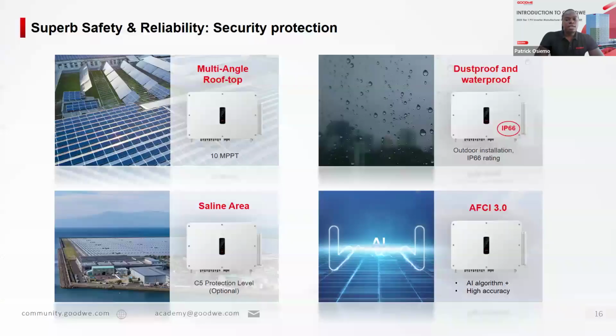Now, with the outdoor features comes a number of benefits. For example, protection from rain, humidity, and if you're installing in a very saline area that's humid, then you have the option of increasing your protection level to corrosion 5, C5 protection level. And yeah, you also have the option of including the ARC circuit interrupter version 3, which is actually AI operated. It learns on the ARCs and the surges, so it really checks and predicts what kind of surges are happening in your system. So there's predictability in our AI algorithm.